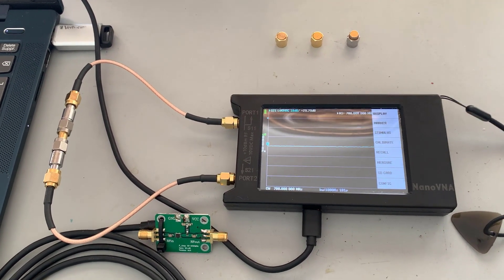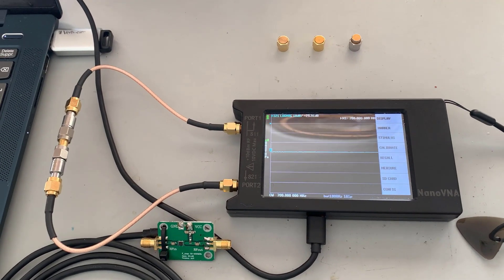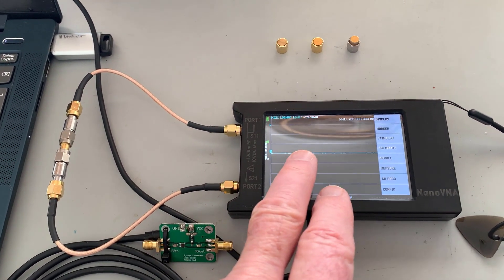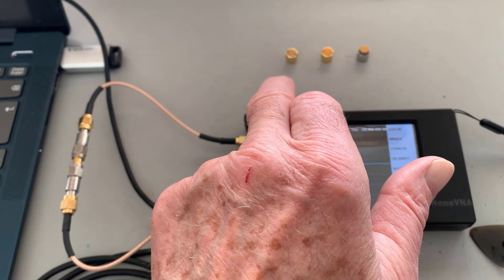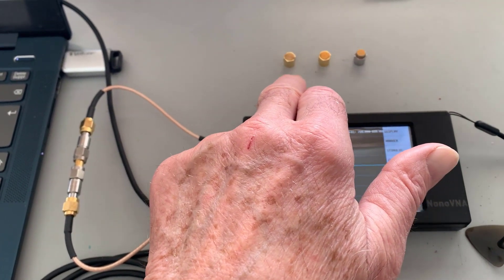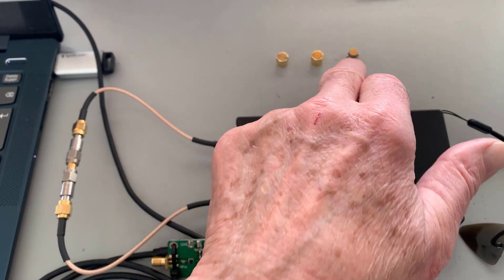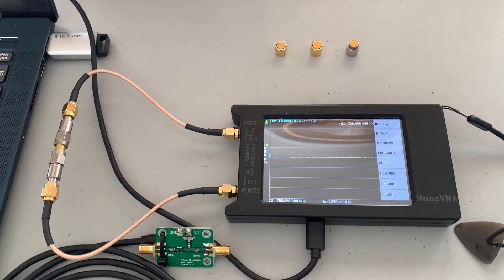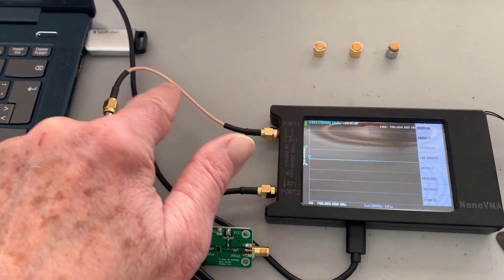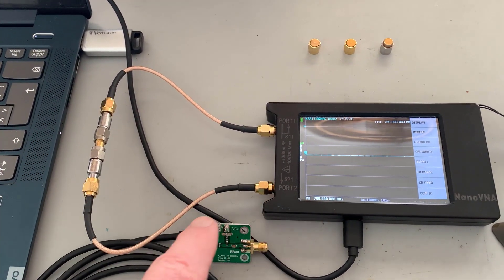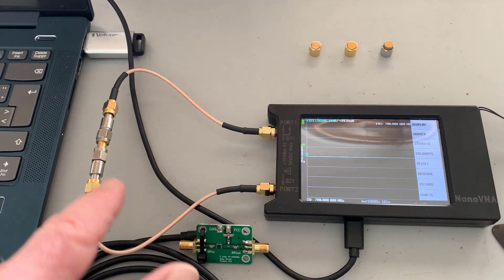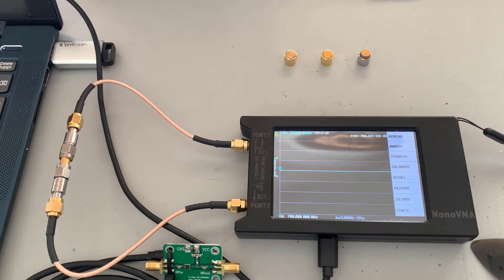I've got the details in the blog post, but what I've done here is I've set the guy up. Incidentally, these are the terminations used to calibrate it. That's the open, that's the short, and that's the 50 ohm. So I've also got two cables in here, two SMA cables. Right now I've got a 30 dB pad in between.